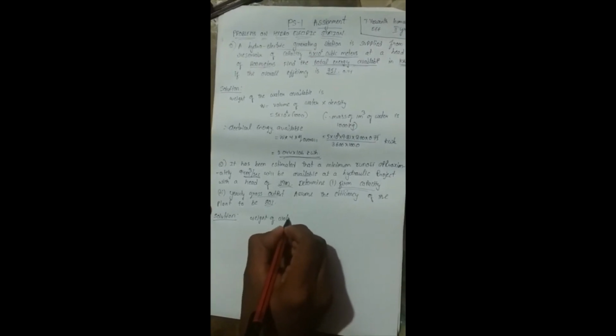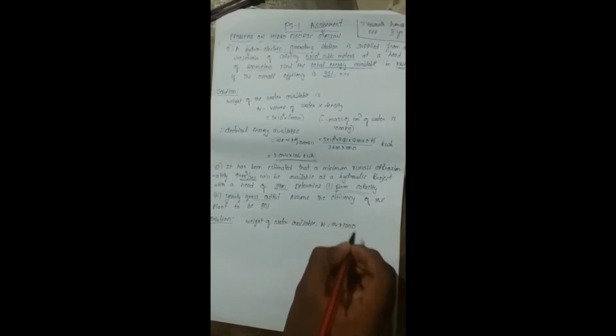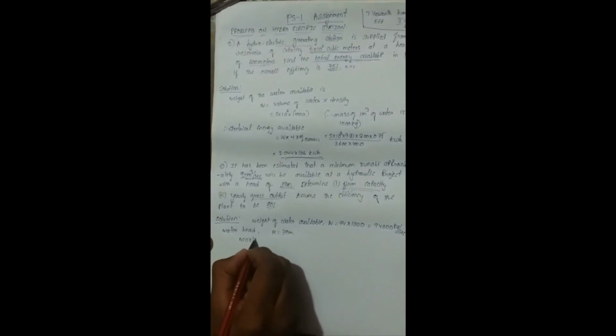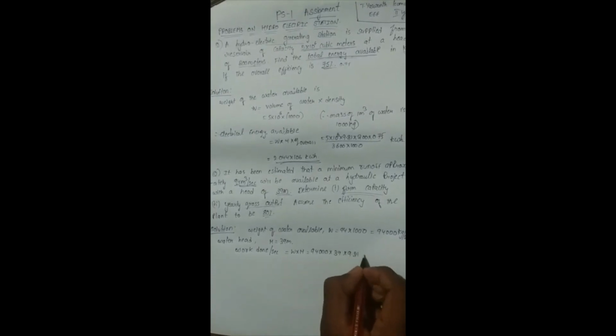Here the weight of water available, W, is equal to 94 into 1000, as 94 is the volume and 1000 is the density, we have 94,000 kilogram per second. And water head H is equal to 39 meters. Work done per second is equal to W into H, that is 94,000 into 39 into 9.81 in watts. That is equal to 35,963 into 10 cube watt. On simplification we get it as 35,963 kilowatt.